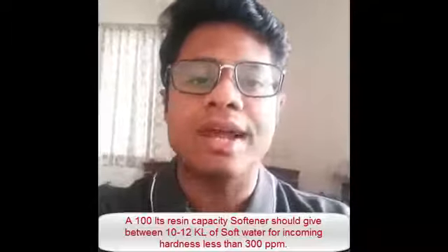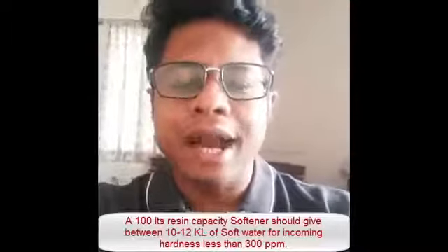How much volume will a softener give? For 100 liters of resin, if your incoming hardness is say 300, it should give 8 to 10,000 liters of soft water. It can be extended to 14 or 15,000 liters if you don't want very soft water. If you have an apartment with a softener of 1,000 liters resin capacity, it will give almost 1 lakh liters of water if your incoming hardness is between 250 and 300. You will need around 250 kgs of salt per regeneration, which means every 1 lakh to 1.5 lakh liters, people have to put in 250 kgs for regeneration.